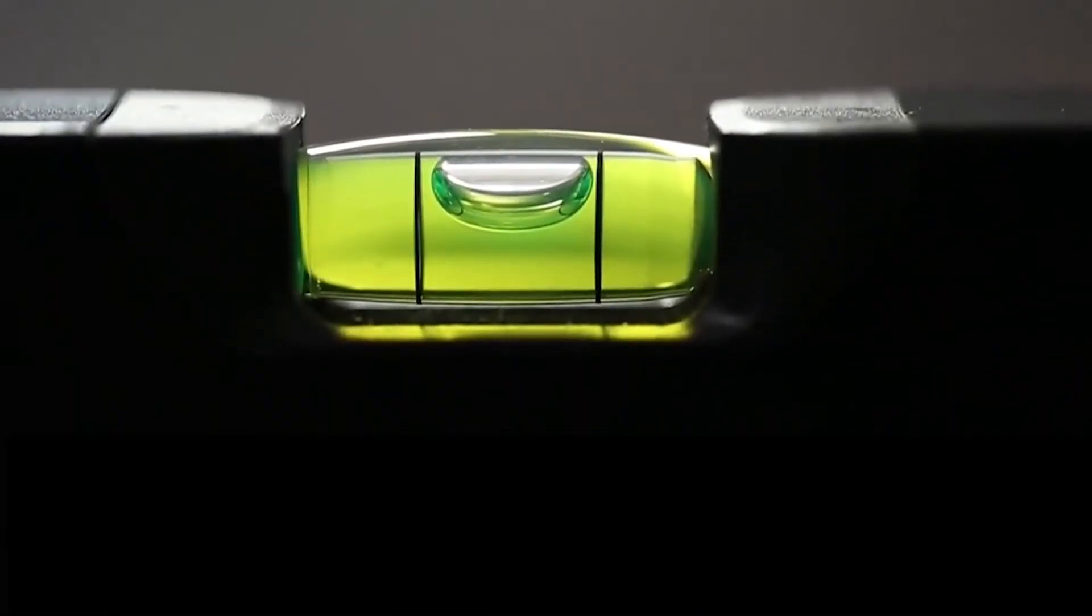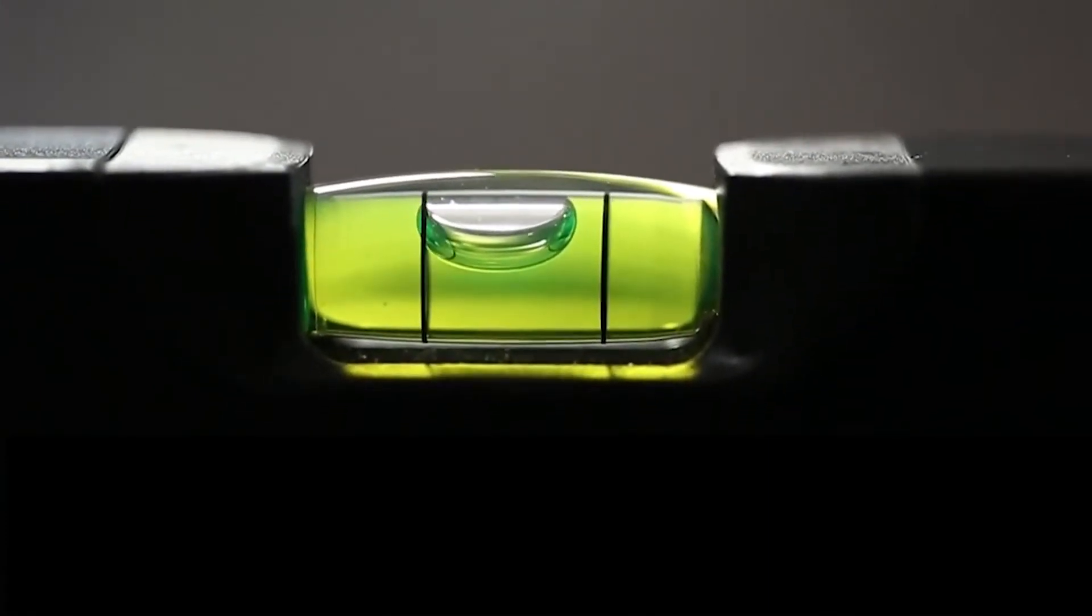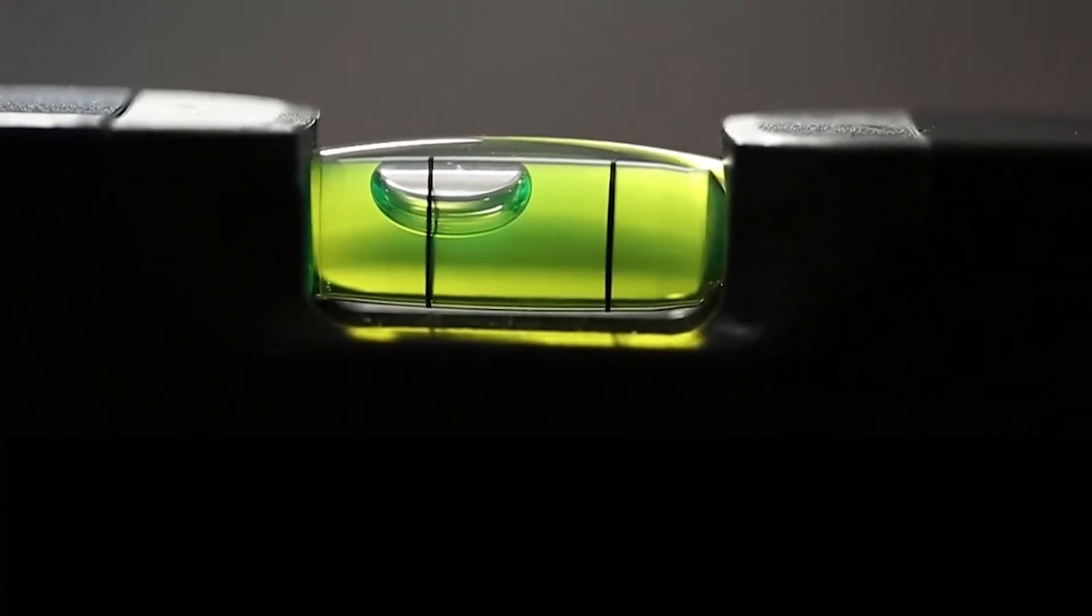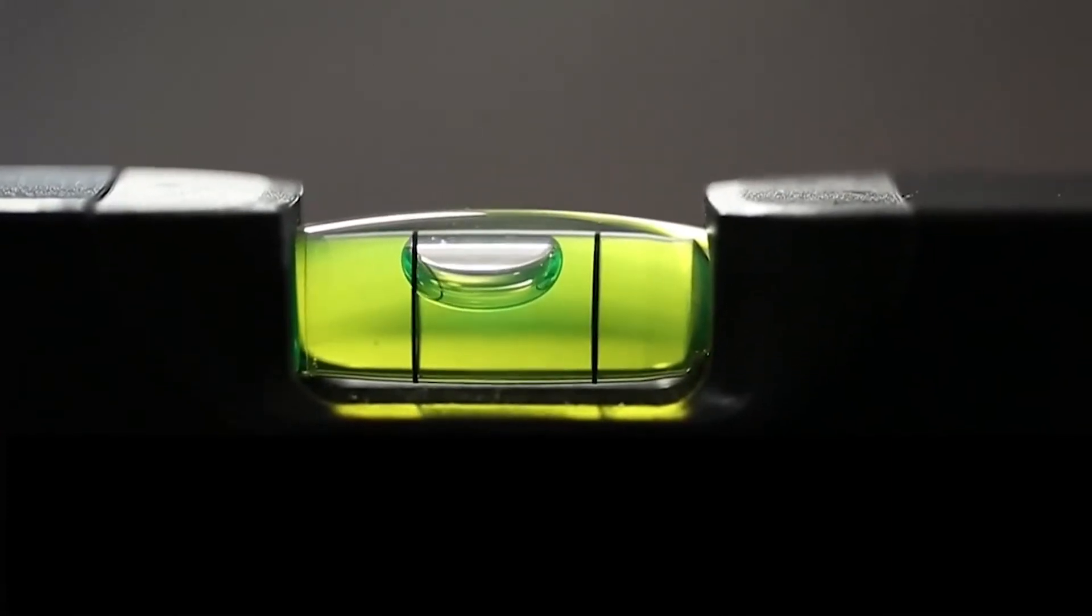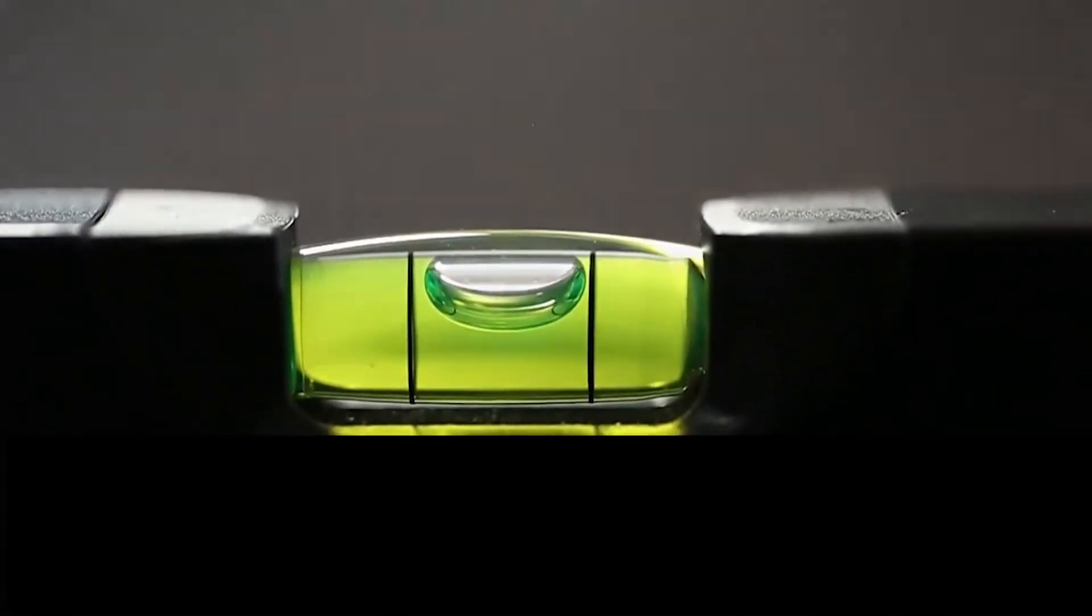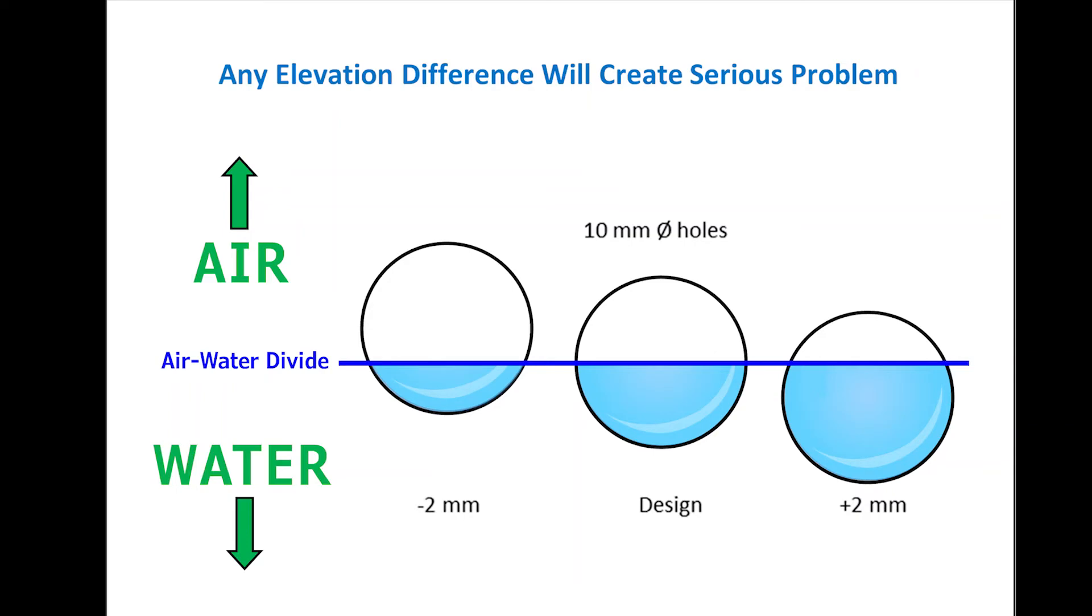Though contractors try their best to have a false floor to be completely level, in reality it's not. Most industry specifications allow plus or minus two millimeters. This graphic shows that a floor elevation variance can undesirably create significantly different airflow rates from nozzle to nozzle.